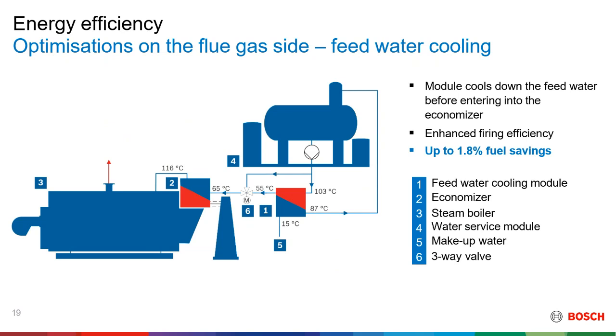Okay. Then another option for saving potential is cooling the feed water. So here, once you have a setup with 2 heat exchangers, so one is the economizer, which is number 2, and then we have a feed water cooling module, number 1. Then we have the boiler itself, the feed water tank, and a 3-way modulating valve. With this, you'll get around 1.8% saving potential. And again, here how you're saving energy is as water is flowing from your treatment plant into the feed water cooling module, it cools down the water that is leaving the feed water tank flowing into the boiler.